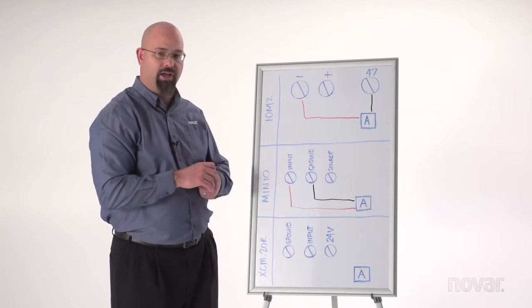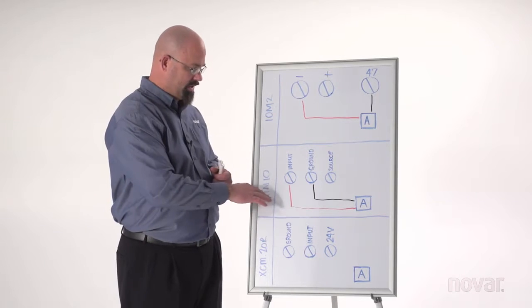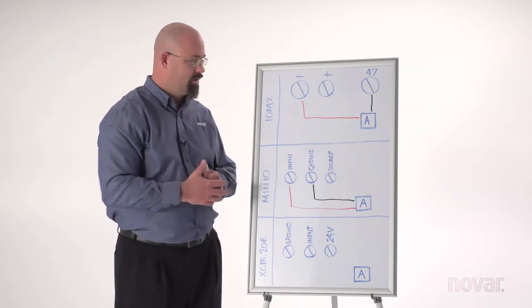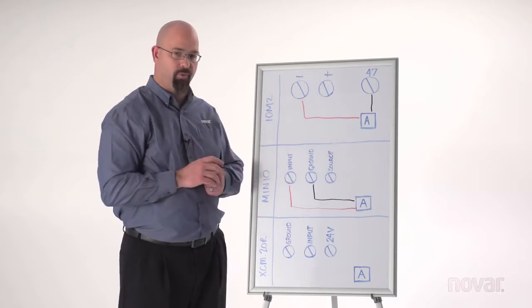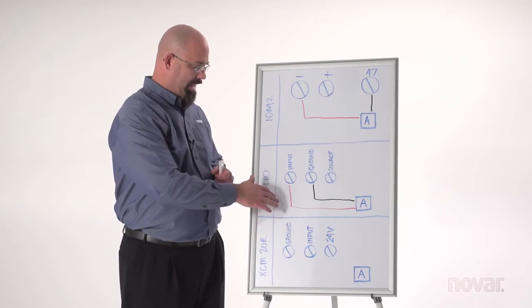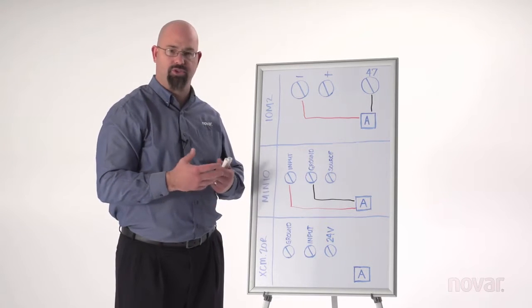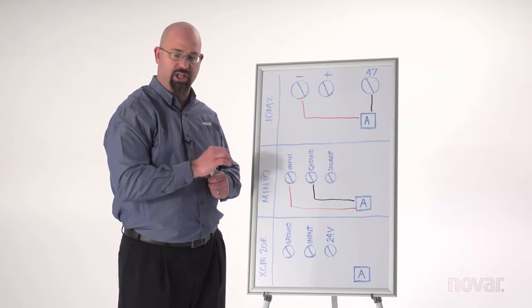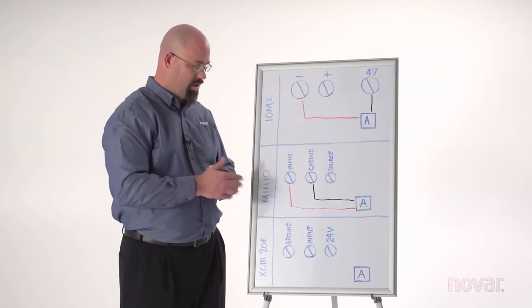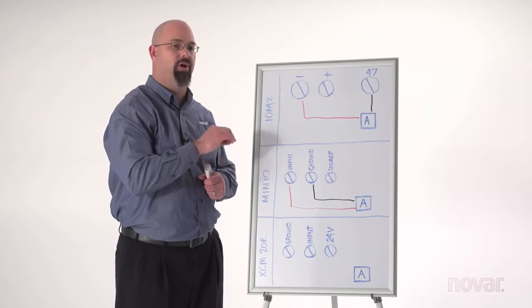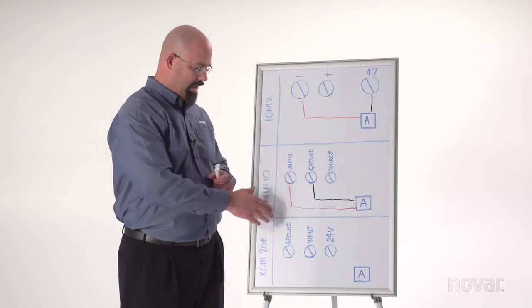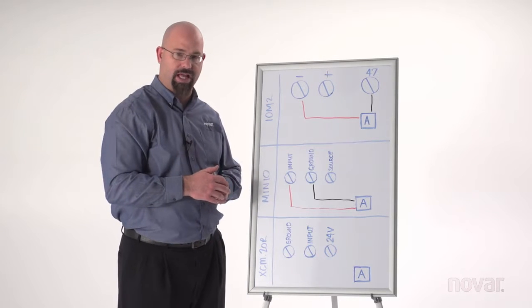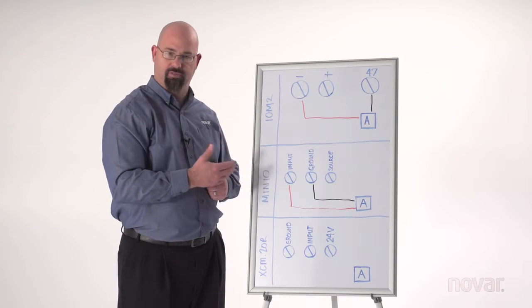Now one exception with this MIN-IO versus the IOM here is this is more universal inputs. The IOM-2 can only be a 4 to 20 milliamp. With the MIN-IO this can be 4 to 20 milliamp, 0 to 10 or 1 to 5. Here we'll have to move that jumper on each of the six universal inputs. So if it was a 4 to 20 milliamp we'll put that jumper on I or 4 to 20. If it was a 0 to 10 or 1 to 5 we'll put that jumper on V for voltage.